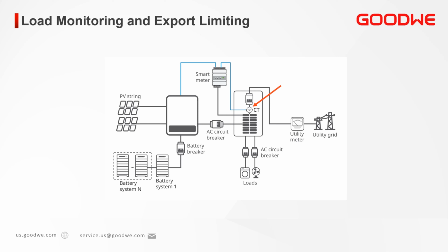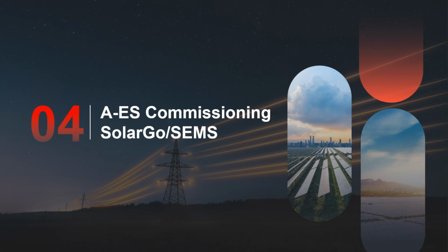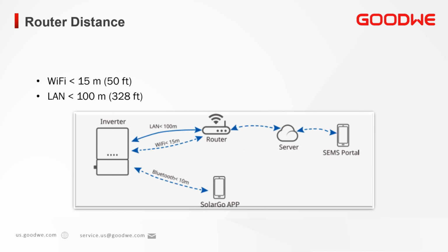Please contact our after-sales support to get more information. There are other uses for the meter in regions where solar power export is regulated or not allowed. This is known in the industry as zero export, but we call it power limiting. Another use for the meter is when you have a small main but cannot do an upgrade. You can then limit the export power of the inverter to meet the limited size of the main entrance. In the next sections, I'm going to be talking about AES and AVP commissioning and monitoring.